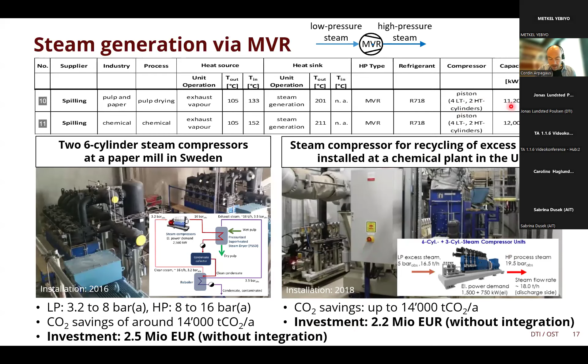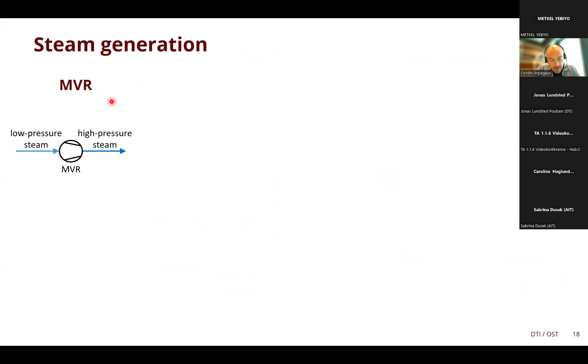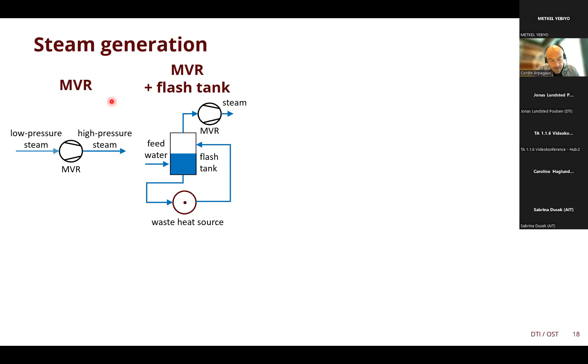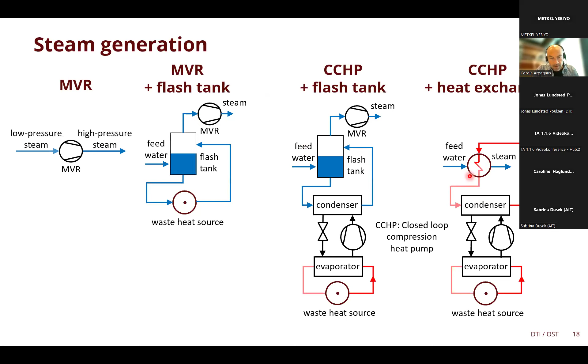So for steam generation, there are various heat pump concepts. We will see it later on as well. But the first one we need to consider is MVR, so mechanical vapor recompression. Then we have, as a second, a combination with MVR and a flash tank, where water is the refrigerant or the working fluid. The third is a closed cycle compression heat pump with a flash tank and MVR. And the fourth concept is a closed cycle heat pump with a direct heat exchanger to generate the steam. So in the following, we have some examples for all these cases.